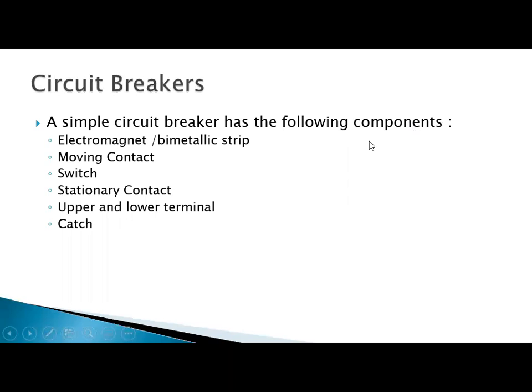So here are some of the items inside of it. It does have an electromagnet that is going to help us with our fault current or short circuit current. It is going to have a bimetallic strip, which is going to help us with overloads. It's going to have a moving contact, because at times my circuit breaker is going to be open and at other times it is going to be closed. So we've got to be able to move some contacts to close and open those. It can act as a switch if it is marked SWD or HID. Circuit breakers have many markings on them. SWD, switching device, and HID, high intensity discharge lighting, both allow the circuit breaker to operate as a switch.